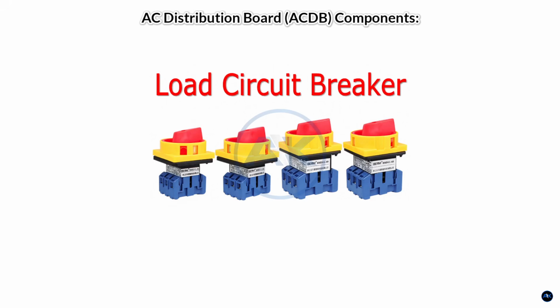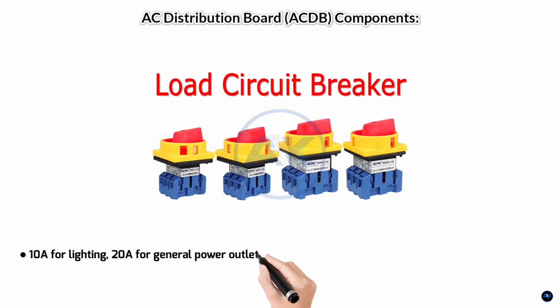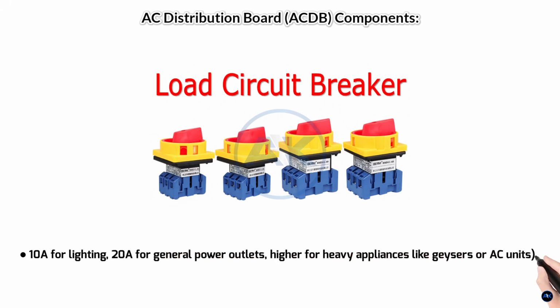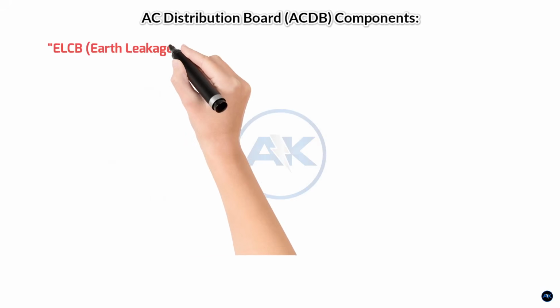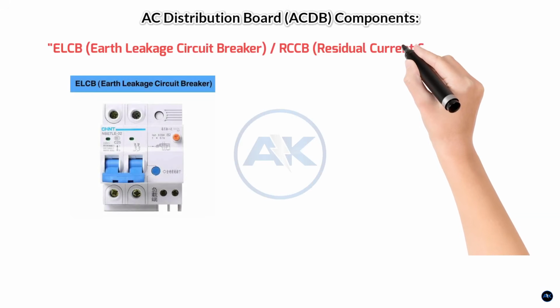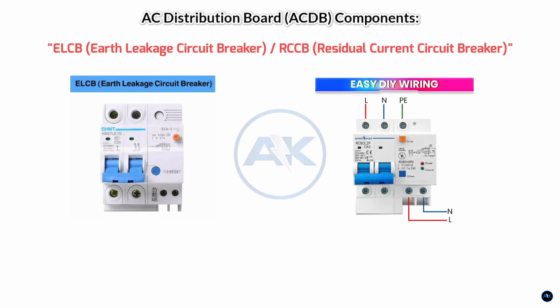Their sizing depends on the connected load and wire gauge as per standard electrical practices. 10 amps for lighting, 20 amps for general power outlets, higher for heavy appliances like geysers or AC units. Your existing HomeDB likely already has these. ELCB earth leakage circuit breaker / RCCB residual current circuit breaker.